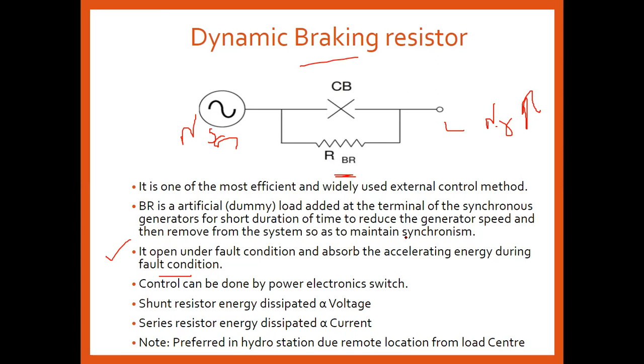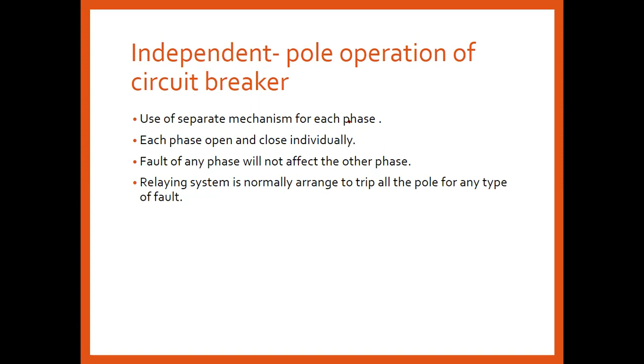Independent pole operation of the circuit breaker. The next method is pole operation of the circuit breaker, using a separate mechanism for each phase. If I use a separate mechanism for each phase, automatically its fault clearing time will be less. If the fault clearing time is less, automatically what happens to the stability? It improves. So by maintaining the pole operation separately for each circuit breaker, a fault in one phase does not affect the other phases. It directly implicates the transient stability of the system.